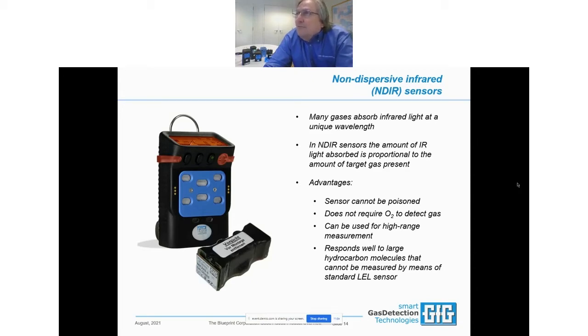There are a number of products that use a micro-miniaturized chip-based IR sensor with an optical path length of a fraction of a millimeter in length. That doesn't give the molecules you're trying to measure much chance to absorb, and that means that it has almost no ability to detect gases that don't absorb really strongly. Those tiny little chip-based sensors are designed for the measurement of one thing, and that one gas is methane. If it is any other kind of gas, the readings are either much, much, much lower than actual if they respond at all, or the response is wildly variable and higher than actual.